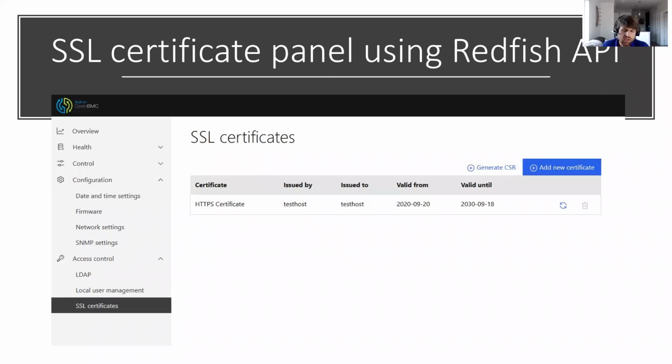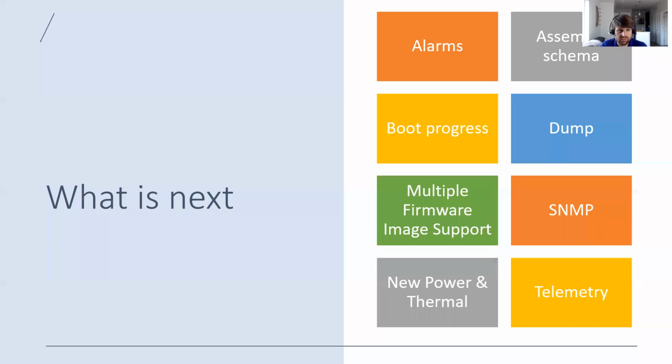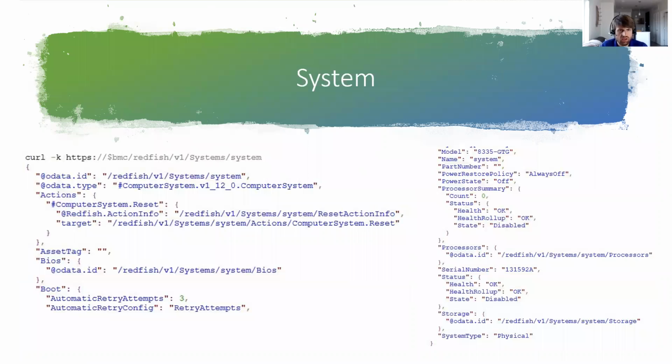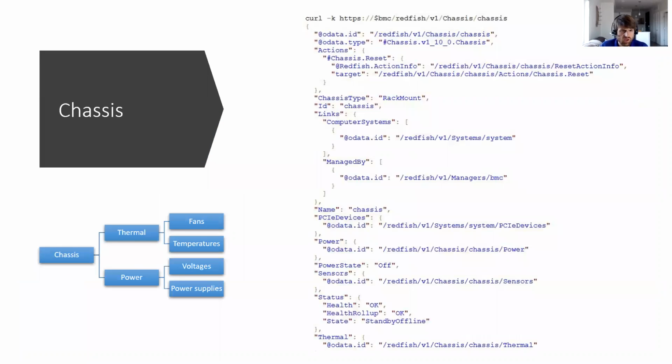Couldn't come off mute. Not today. So Redfish actually uses the sensors collection. Let me pull up chassis here. Okay, so Redfish uses sensors, and I can throw this on IRC, but Redfish says that sensors should only contain sensors that aren't already in thermal and power.